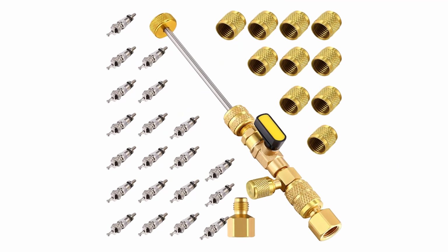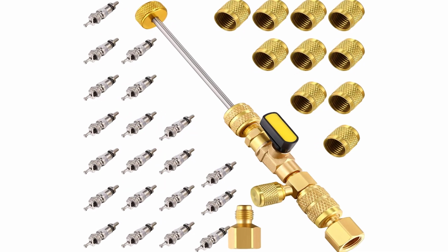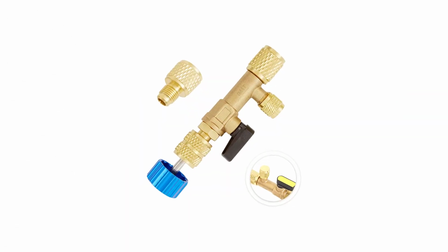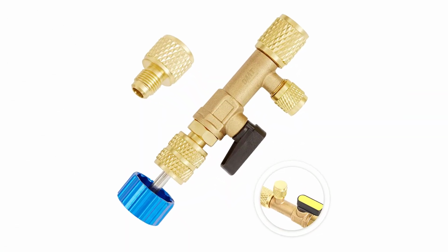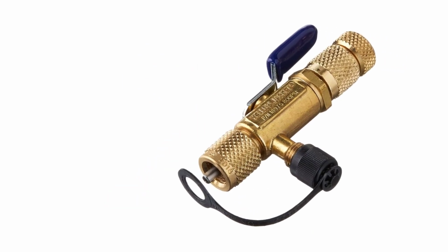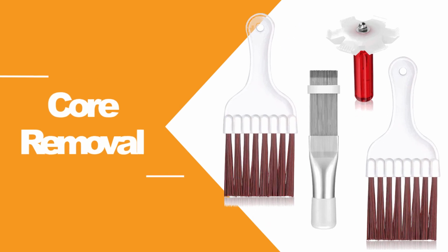Core tools are one of the most important components of a proper evacuation rig. Removing the cores allows for a full unrestricted flow through the service port, significantly decreasing both evacuation and/or recovery times.